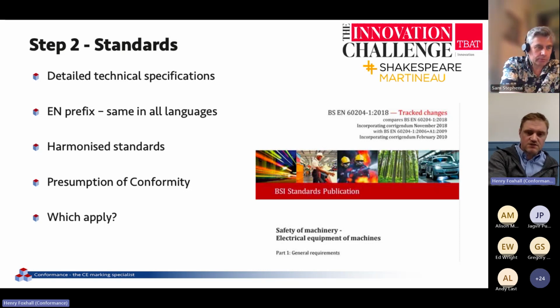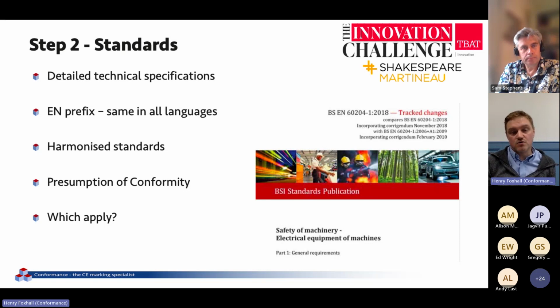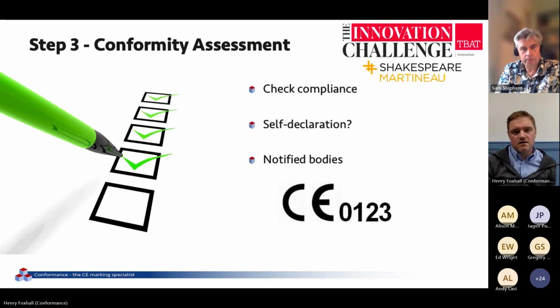So once you've worked out what essential requirements you need and what you need to do to control hazards and risks associated with your product, then go and look for the standard that tells you how to control those risks most suitably. And then, as we've talked about before, you do a conformity assessment. So usually this takes the form of a checklist. So take each point of the EHSR, the essential requirements of the product directive or the regulation you're using, and show and check that you've complied with each statement on there. And if you haven't complied with them, go and do it. If they're not applicable, mark them as not applicable. Don't just ignore them.